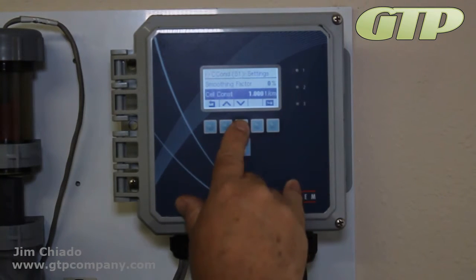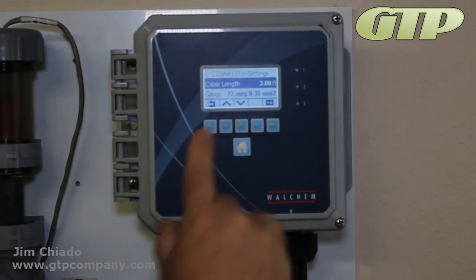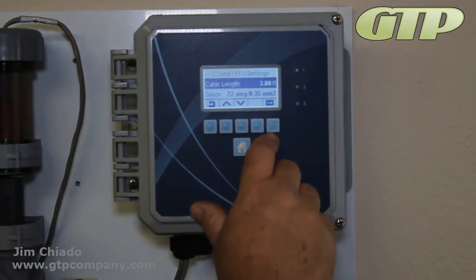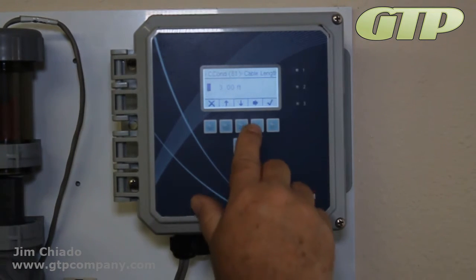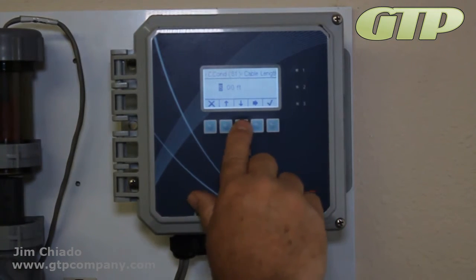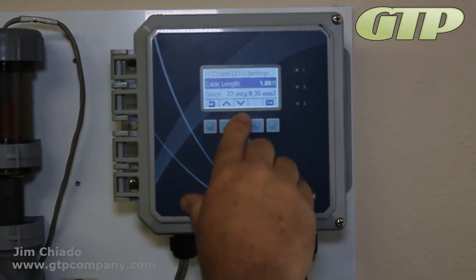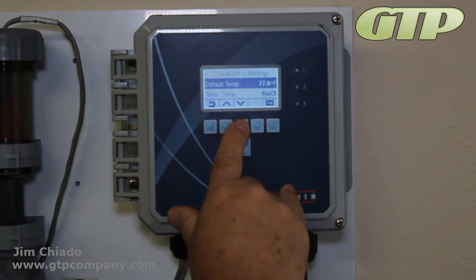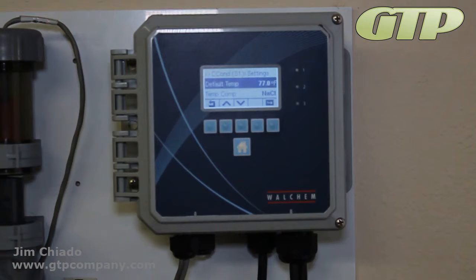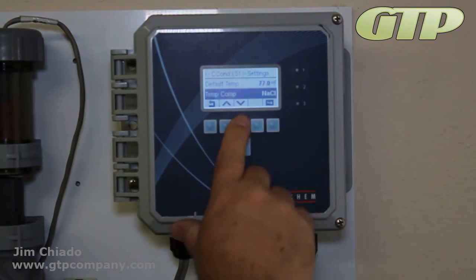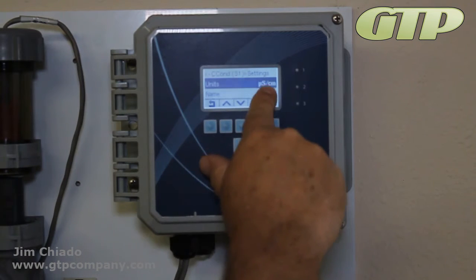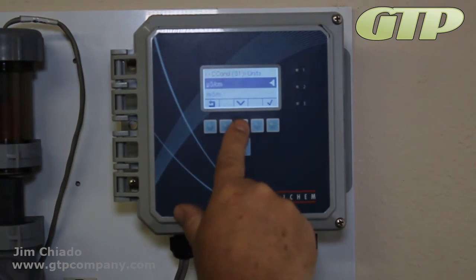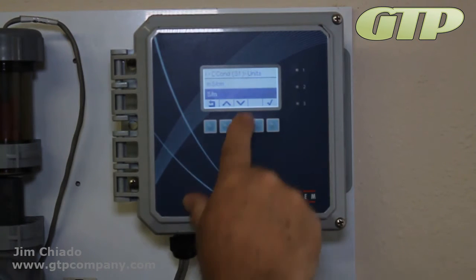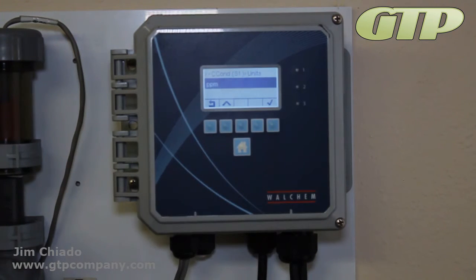Cell constant 1, that is the standard sensor. Sometimes you can switch that out. Cable length 3 foot. This is more like 15 inches or maybe 1 foot. So we're going to change that. This is a short cable. We're going to make it 1 foot. 22 gauge, that's very true. Default temperature 77 degrees. Cool water, maybe it's a little bit warmer. Temp compensation, NaCl. Units of measure: you can change this to read in microsiemens, millisiemens, and even ppm if you want. Okay, we're just going to return back so it leaves it at microsiemens.